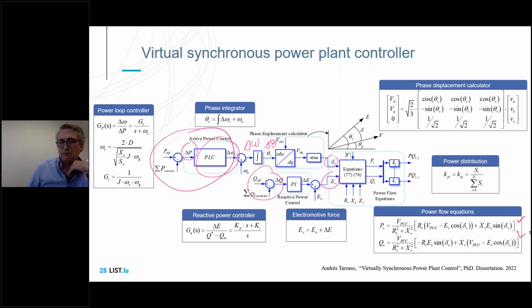Using the formulas we mentioned before, for a given impedance, we can transform angle and amplitude of the excitation into given P and Q. Therefore, this is the P and Q to be developed by the converter, and in this case we are applying this to a plant, not to a single grid forming converter.